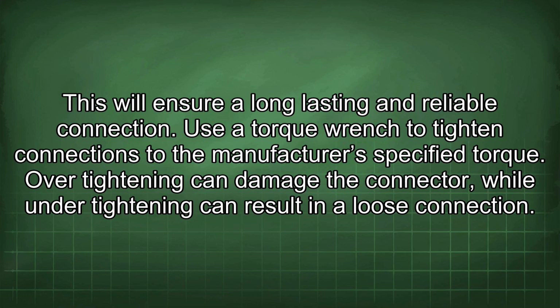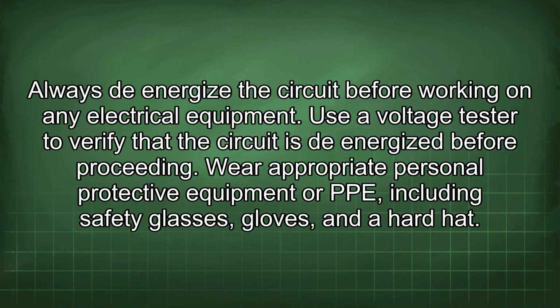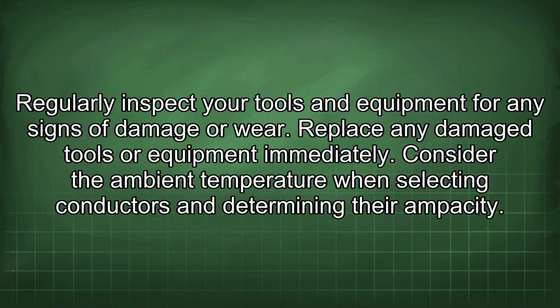Use a torque wrench to tighten connections to the manufacturer's specified torque. Over-tightening can damage the connector, while under-tightening can result in a loose connection. Always de-energize the circuit before working on any electrical equipment. Use a voltage tester to verify that the circuit is de-energized before proceeding. Wear appropriate personal protective equipment, or PPE, including safety glasses, gloves, and a hard hat. Regularly inspect your tools and equipment for any signs of damage or wear. Replace any damaged tools or equipment immediately.